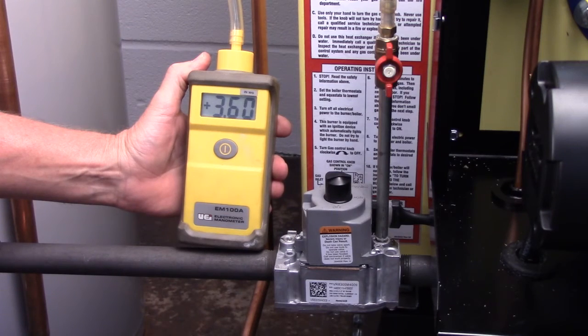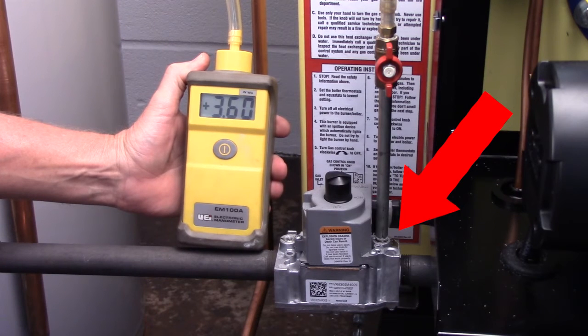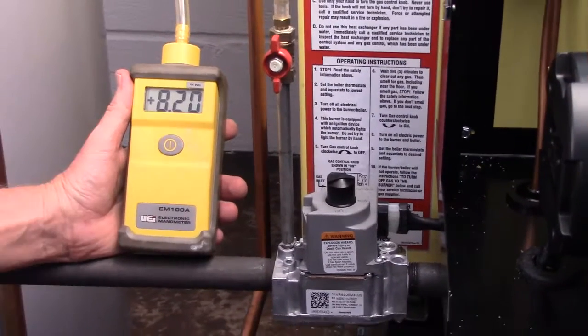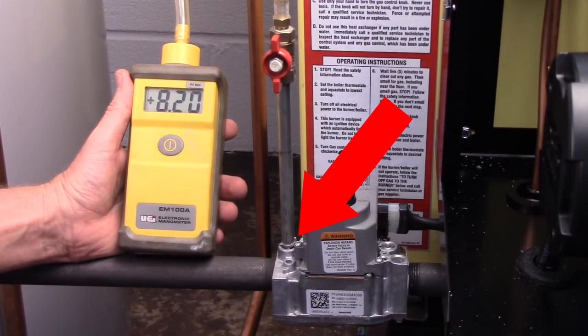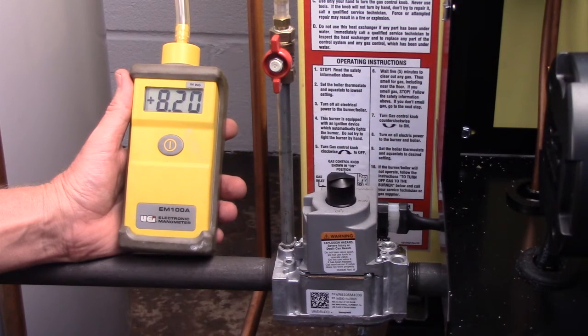Check the gas valve outlet pressure. It should be between 3.2 and 3.8 inches water column. Check the line pressure at the gas valve supply pressure tapping. Gas pressure must be at least 5 inches water column with the burner firing. Adjust the regulator if the pressure is less than 5 inches water column and do not exceed 14 inches water column. If other appliances are on the same line and the burner inlet pressure drops more than 1 inch of water column at light off when they are operating, the gas line is undersized.